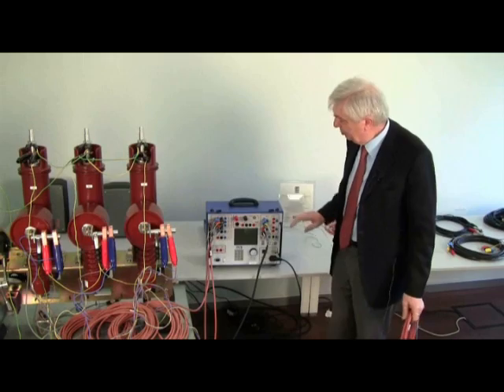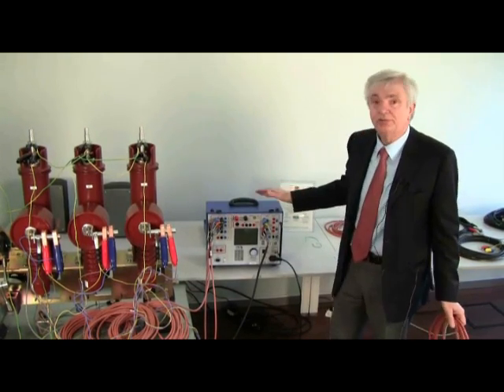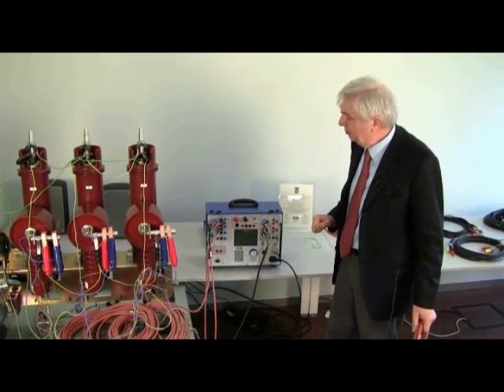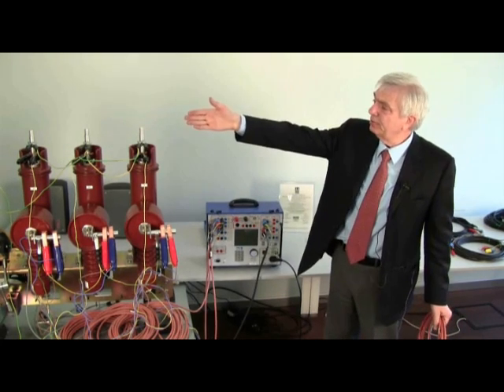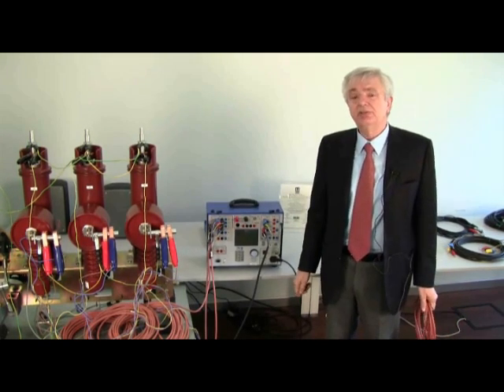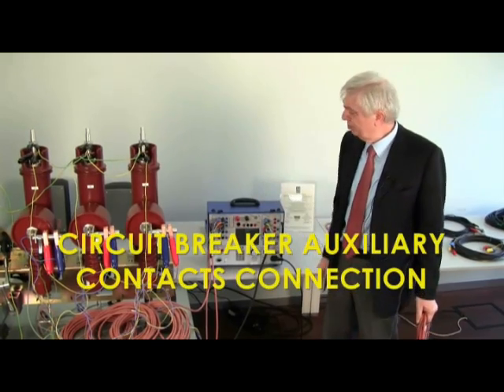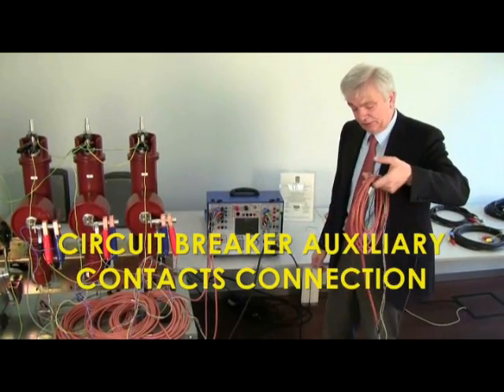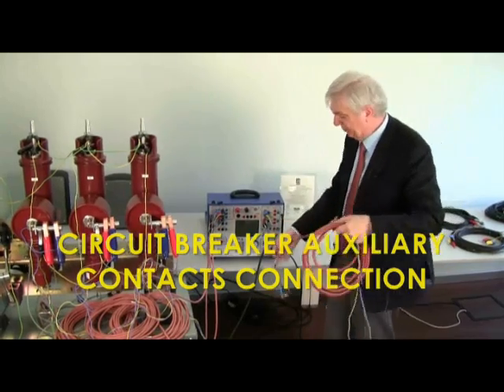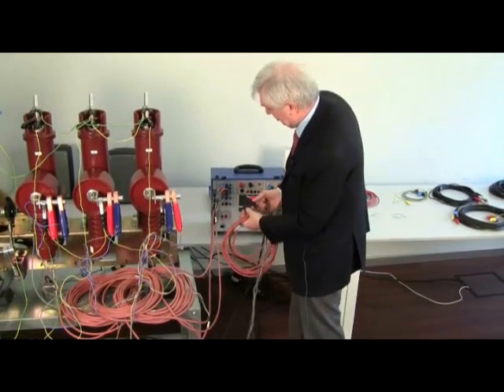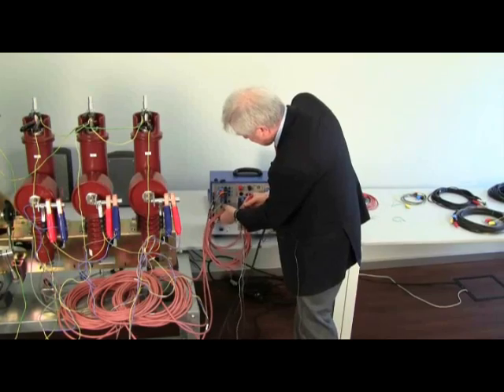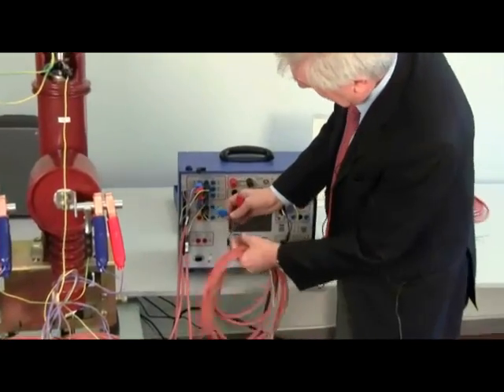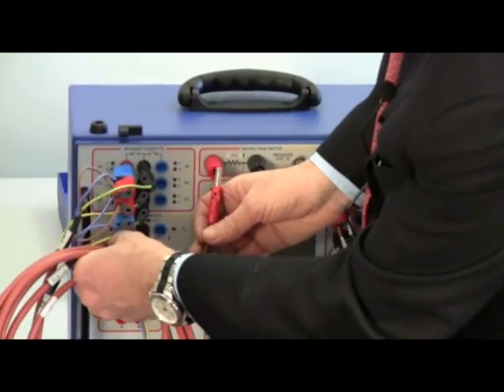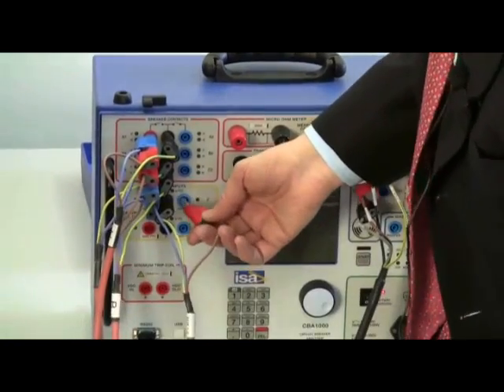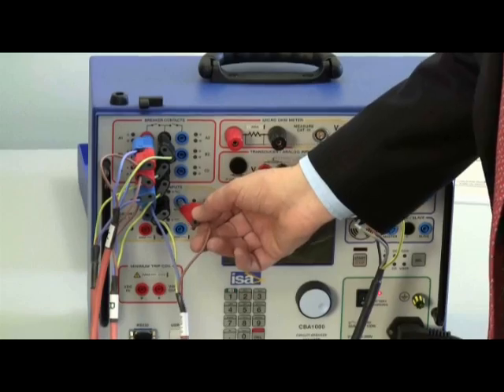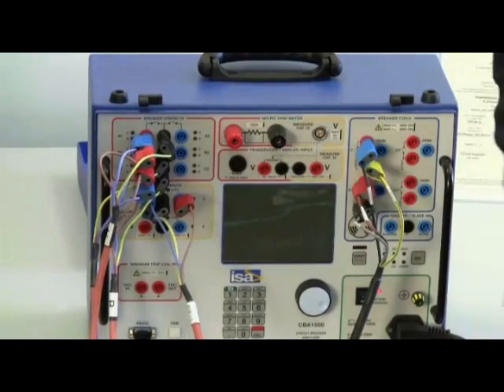Now you see, I could even say that the test set is ready for operation, but as soon as I have available on my circuit breaker the auxiliary contacts that tell the open and close position, I am using this cable here to connect. So what I connect is the black to the common point, and then, for instance, the red to input auxiliary 1, and the blue to auxiliary 1, and the red to auxiliary 2.